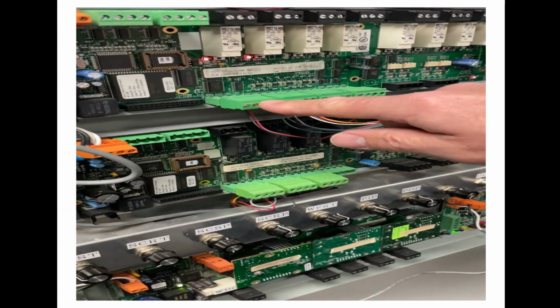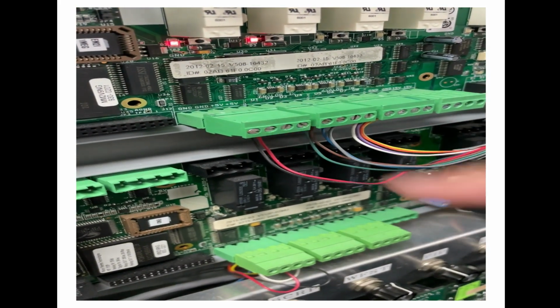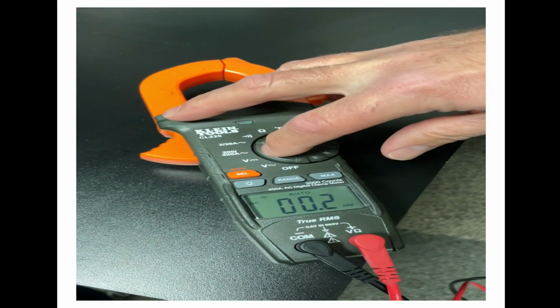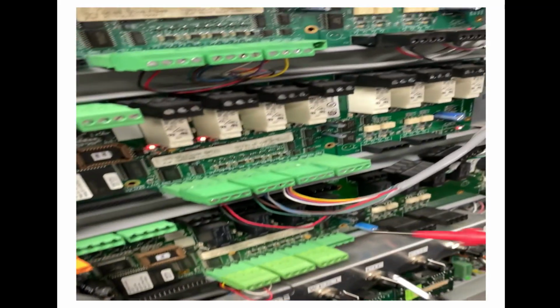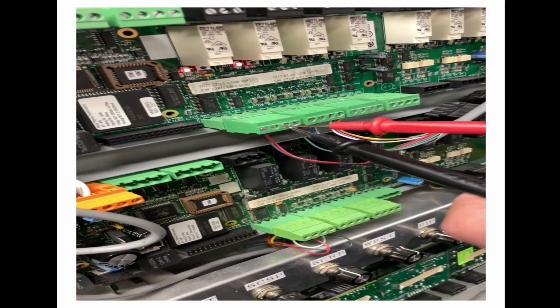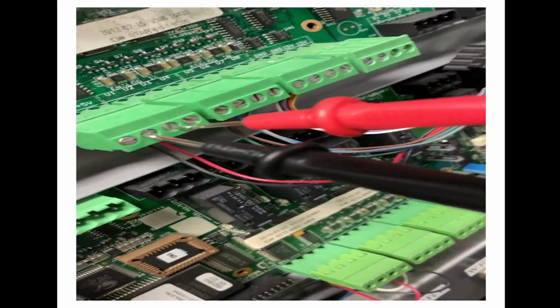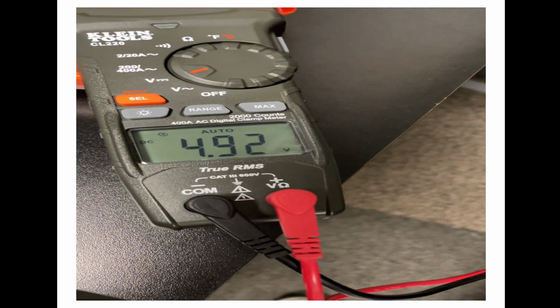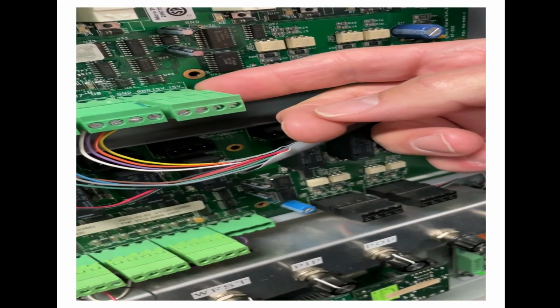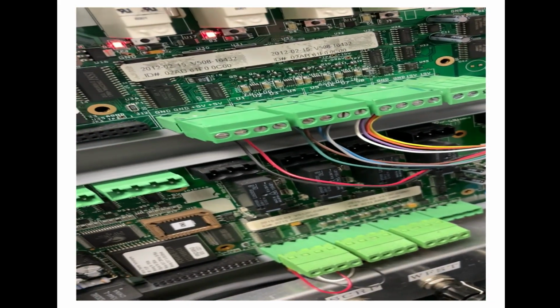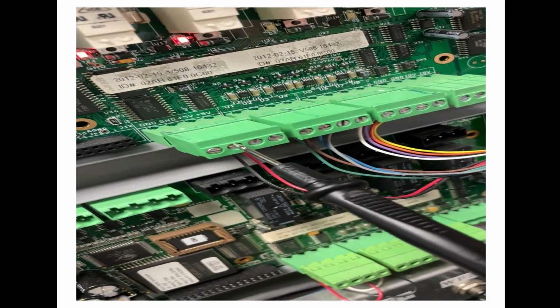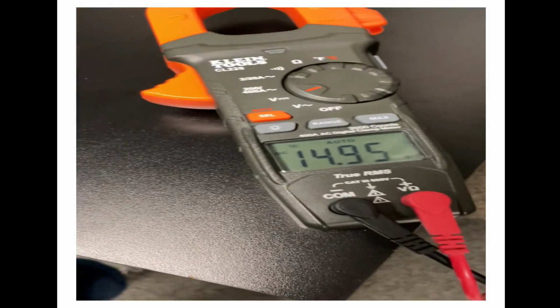Next, we will want to check the internal power supply for thermistors, sensors, and pressure transducers. There's a 5 volt supply and a 15 volt supply. So connect to the 5 volt and ground with a good quality multimeter to make sure you have a 5 volt supply. Then go to the 15 volt channel and check from 15 volt to ground and make sure that you have a 15 volt supply.